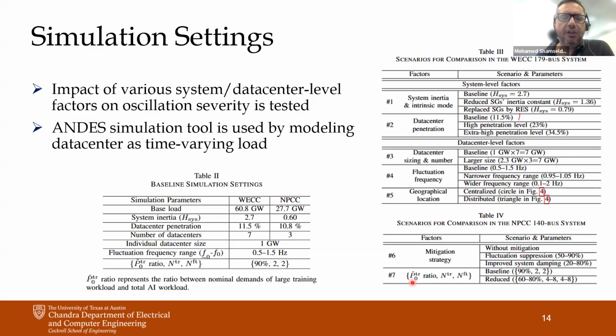So it's 10% of the total load of the system, basically, or the total generation capacity? The total load of the system, 10% of which is data centers. At this level you start seeing the oscillation, and what you're saying is critical for utilities. If a data center causes oscillations that might cause wide area oscillations, that's a big claim or finding. But saying this only happens when penetration reaches 10% is a totally different story than just 1% or 0.5%. That's what I'm trying to say.